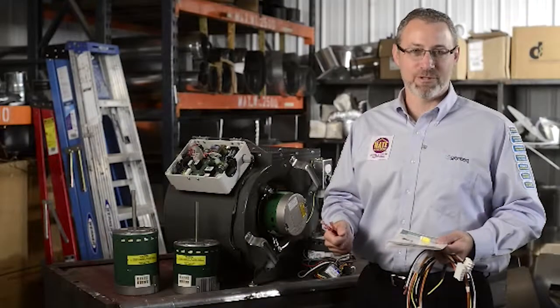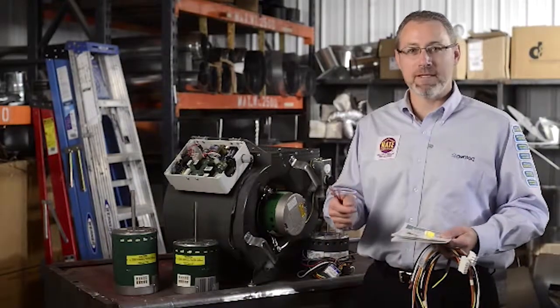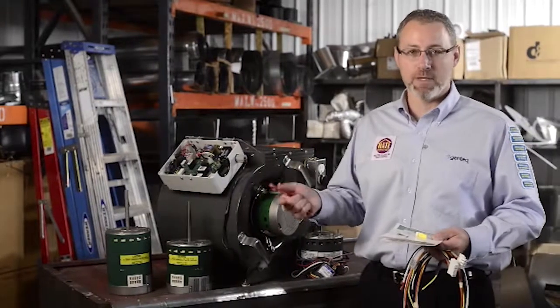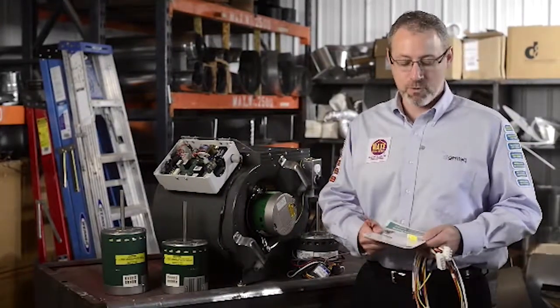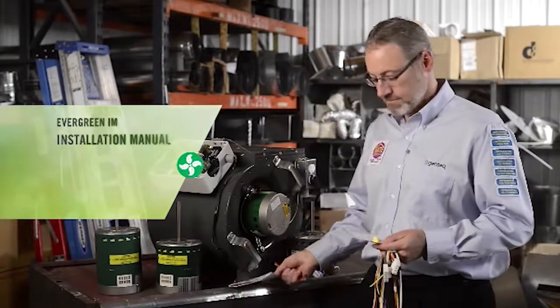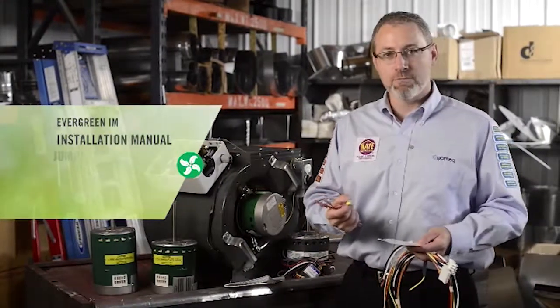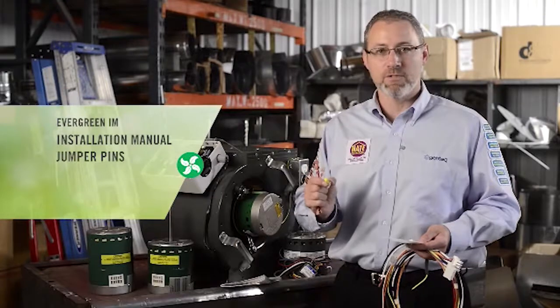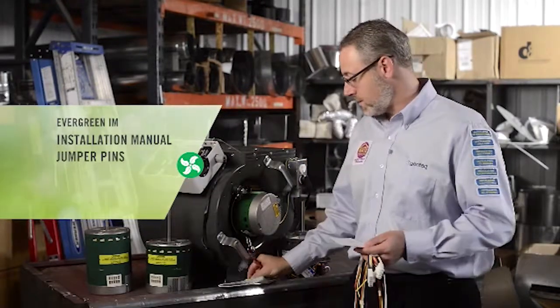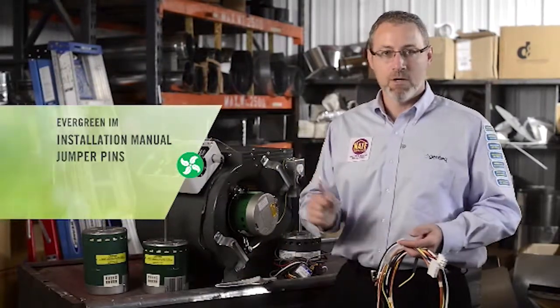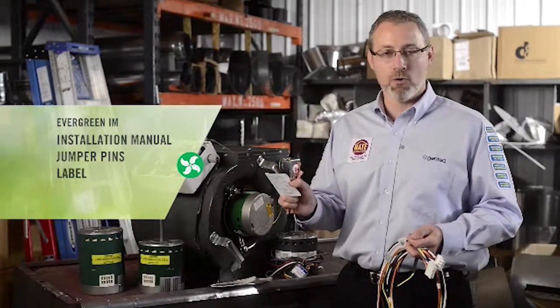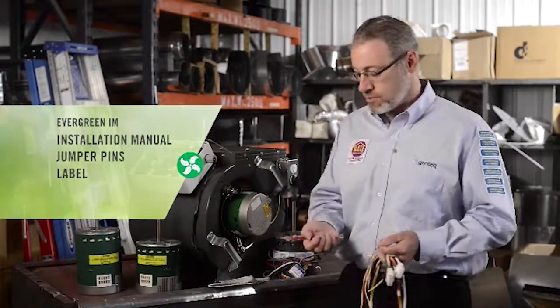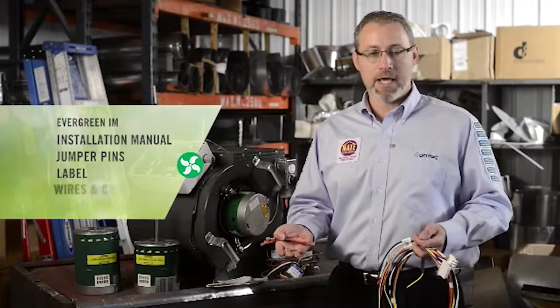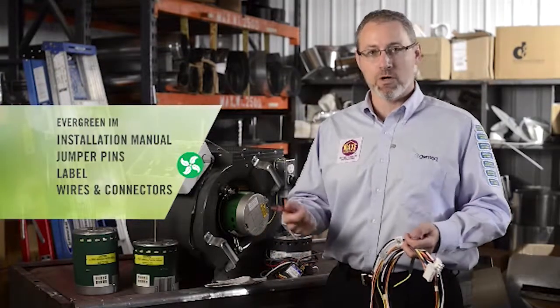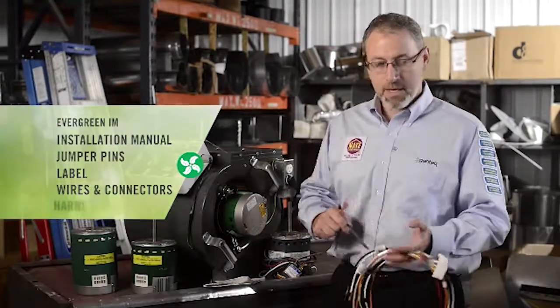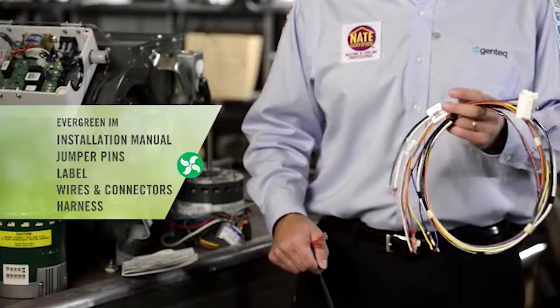Let's talk about electrical connections. But before we begin, let's look at what comes in the box with the Evergreen IM. Of course, the installation manual. Being a dual voltage motor, we have jumper pins, one for 115 volt and one for 208, 230 volt applications. What I would consider a required sticker or label to install in the HVAC system, some optional wires and connectors, depending on how you are going to configure the system, and the main harness that connects the Evergreen IM to the HVAC system.